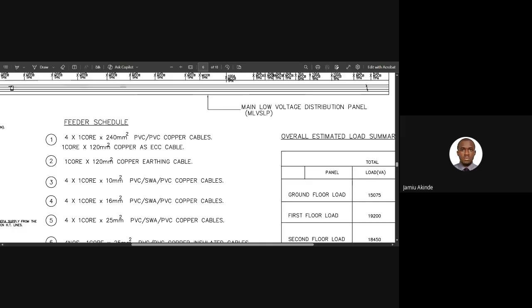Okay, let me explain. When they say 4 by 1 core, it is not 4 core. That 240 mm is 1 core. Now you have 4 runs, that cable will now go in 4 places. That's what they call 4 by 1 core by 240 mm cable. It is not 4 core by 240 mm cable. If you're talking about 4 core, it shows that in one run, in one cable, you'll see 4 different cables. But when they tell you 4, it shows that if you get 100 meters, you slash it by 4. It shows that cable will run in 4 places. Do you get my explanation?